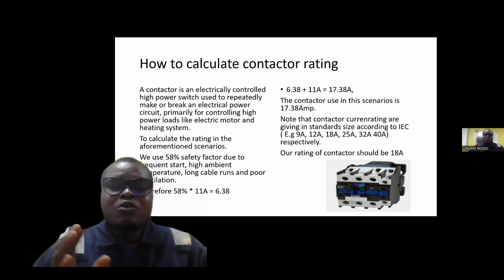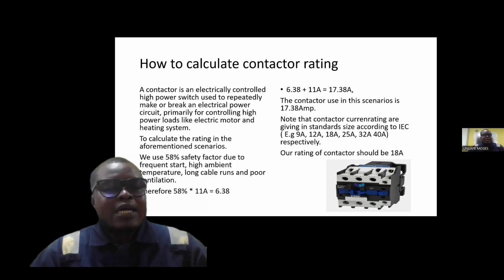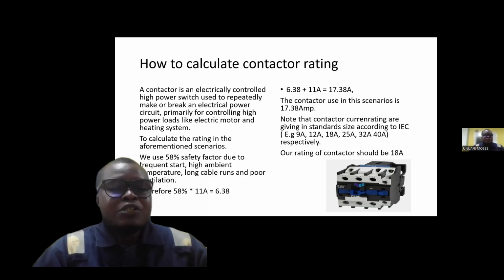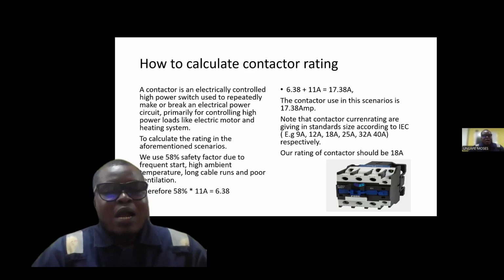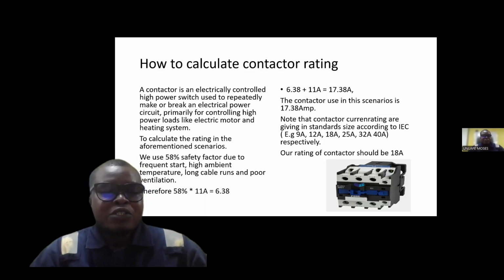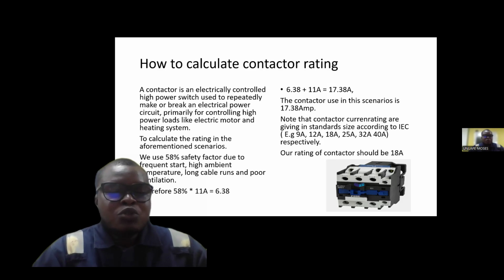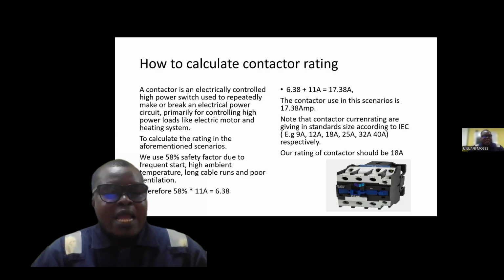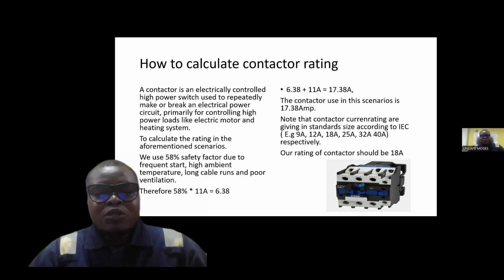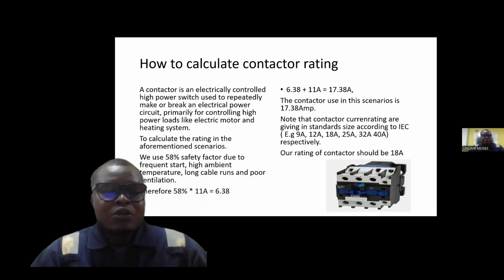Then how do we calculate the contactor rating? Before we can talk about calculating the contactor rating, we need to know what a contactor is. A contactor is an electrical control high power switch used repeatedly to make and break an electric power circuit, primarily for controlling a high power load like an electric motor and heating system. Now, to calculate the rating for this scenario, which is the motor that has been supplied for us previously, we use 58% as a safety factor due to the frequent starts of this motor, the high ambient temperature, the long cable runs, and poor ventilation in the area where it is going to be installed.